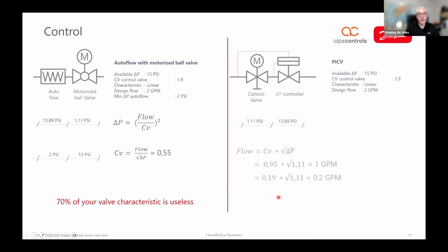And that means that if you have half your CV, which means the valve is half closed, you will have 1 gallon. If you have 20% of your CV, then you have exactly 20% of your maximum flow, which is 0.4 gallon. So, if you have 10%, then you have 10% of your flow. So that is a very different way of working than on the other side.